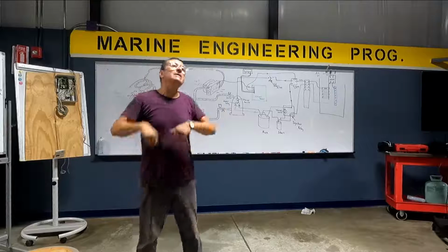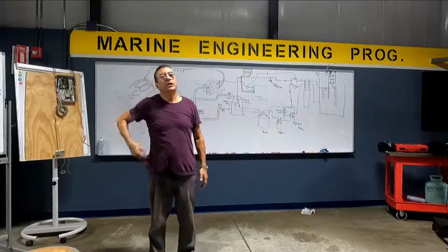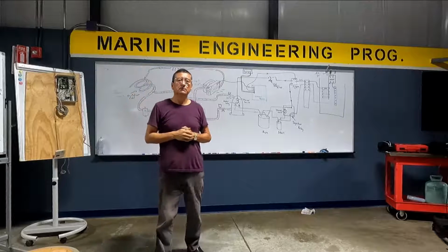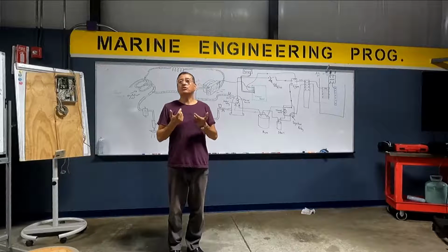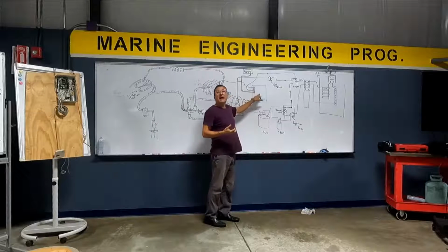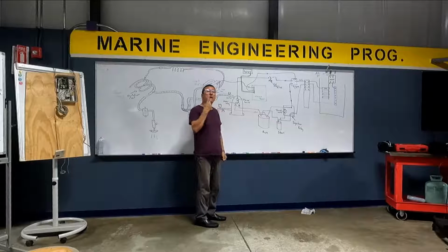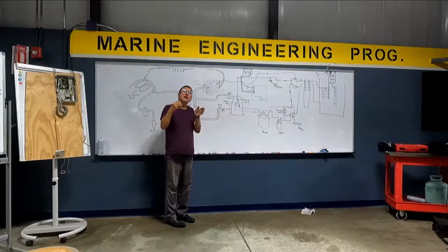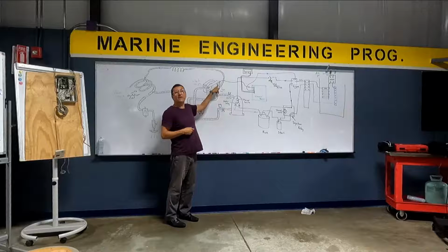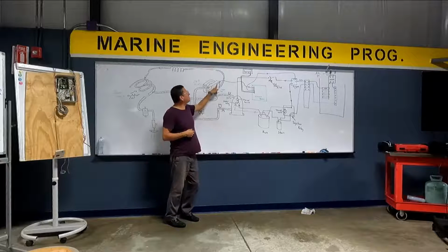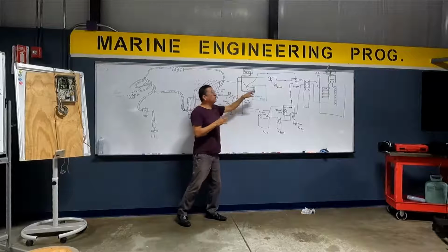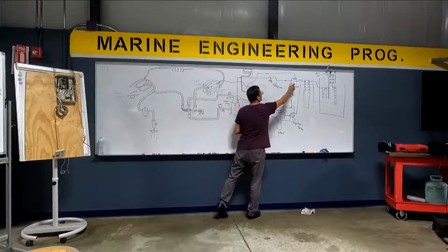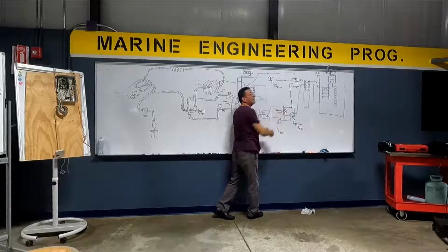When I activate the breaker, immediately the air conditioning unit starts? No. I need to activate what other element? Thermostat. The thermostat. When you select the temperature, the thermostat sends the signal to the computer, and the computer verifies with this sensor located in front of the filter what is the ambient air entering, passing in front of the sensor. With this temperature and the temperature that you select, the computer does the comparison and sends that signal, the blue signal, to the triac and activates the current here and here.